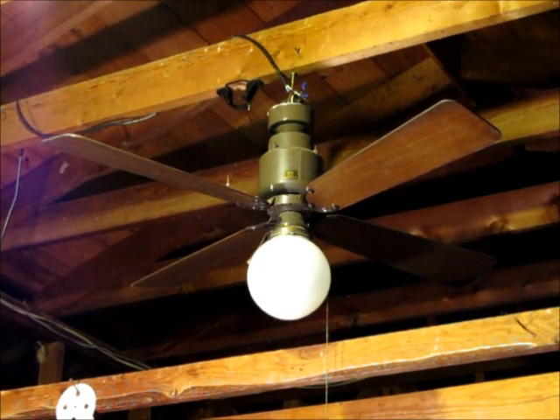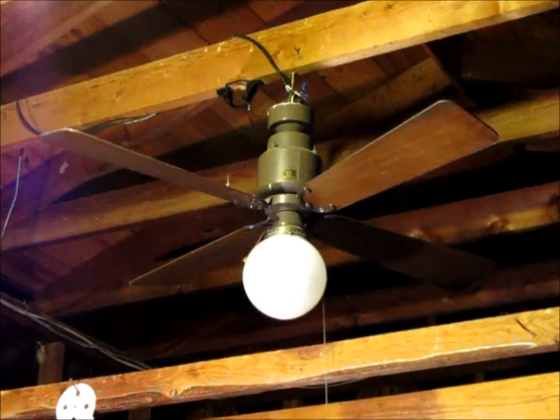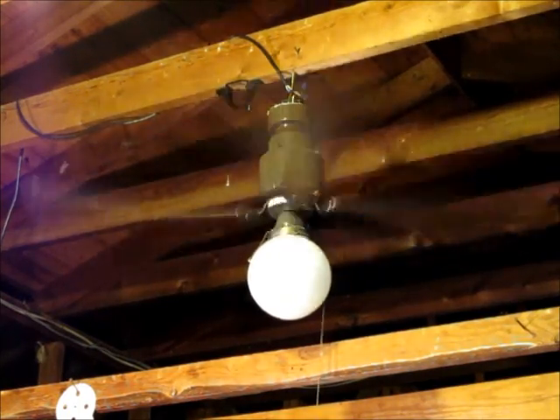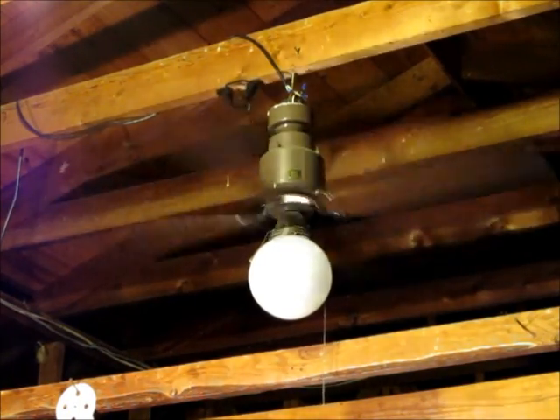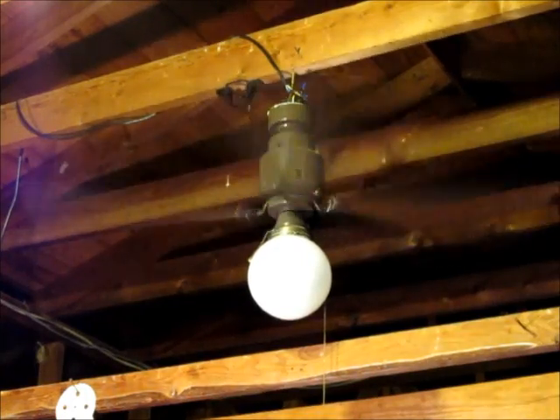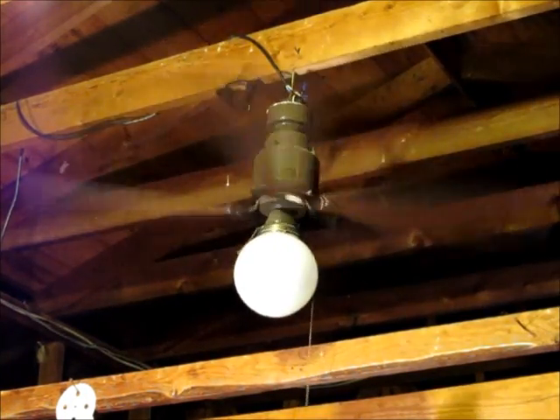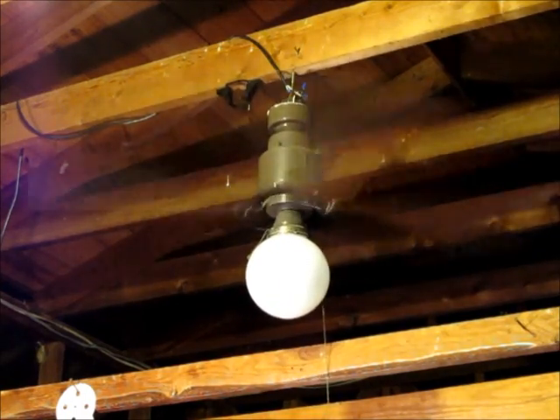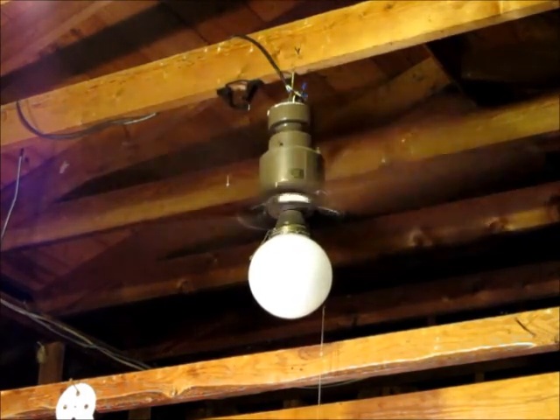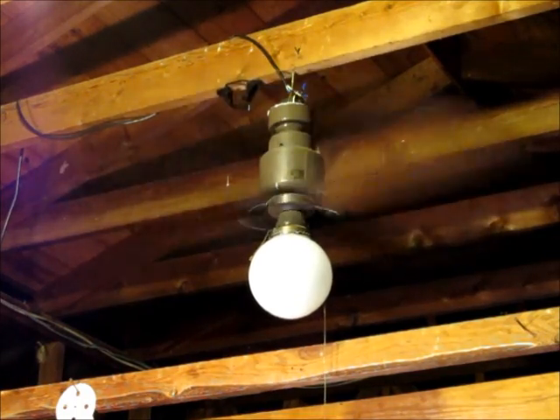Alright, let's have a little fun with a blender fan. What I have done is taken out the 4UF capacitor and put in a 5UF, like apparently the fiberglass plug-ins normally came with. So now we'll see if we can get the speeds closer to what they're supposed to be. Low, about 150 as it's supposed to be. And high, about 220 like it's supposed to be. That 5UF capacitor made all the difference in the world.